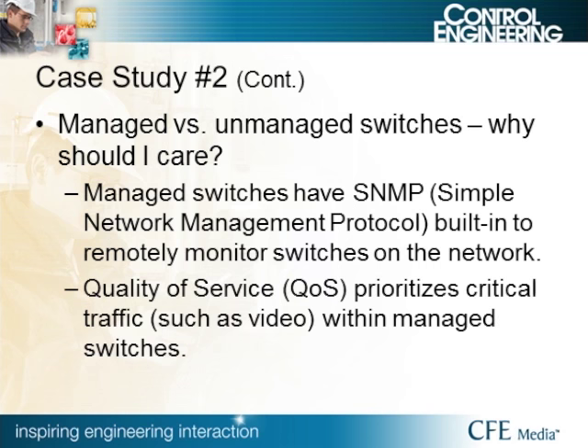Another thing managed switches have is SNMP — Simple Network Management Protocol. This protocol allows different software packages to monitor switches on the network remotely. You can even tie it in through OPC into an HMI. It gives you port status, power supply status, temperature of the switch, and a wealth of other information, so you have some idea of how your switches are performing out in the field. With an unmanaged switch, you typically won't know it's failing until it fails.